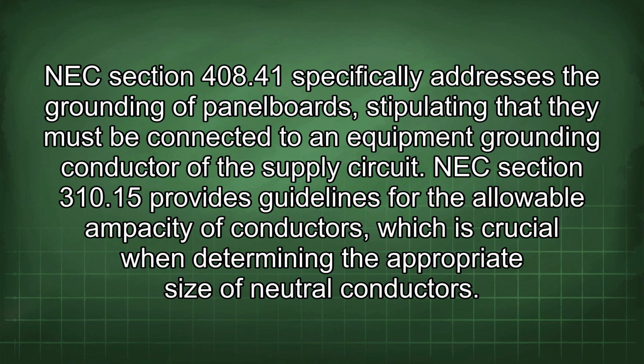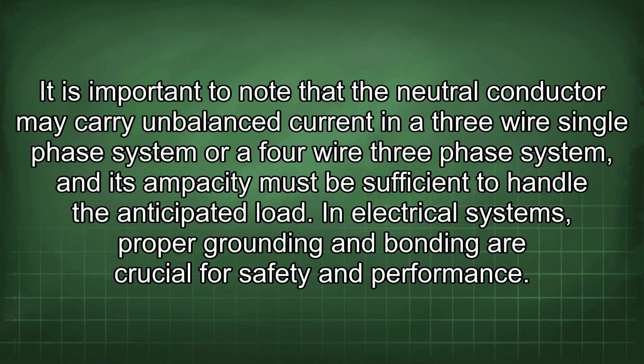NEC Section 310.15 provides guidelines for the allowable ampacity of conductors, which is crucial when determining the appropriate size of neutral conductors. It is important to note that the neutral conductor may carry unbalanced current in a 3-wire single-phase system or a 4-wire 3-phase system, and its ampacity must be sufficient to handle the anticipated load.